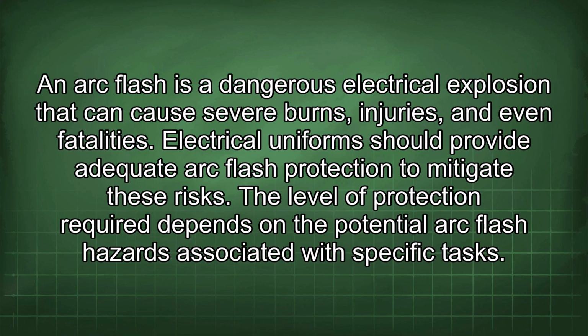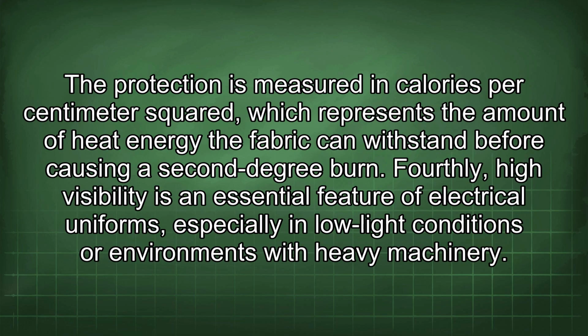An arc flash is a dangerous electrical explosion that can cause severe burns, injuries, and even fatalities. Electrical uniforms should provide adequate arc flash protection to mitigate these risks. The level of protection required depends on the potential arc flash hazards associated with specific tasks. The protection is measured in calories per centimeter squared, which represents the amount of heat energy the fabric can withstand before causing a second-degree burn.